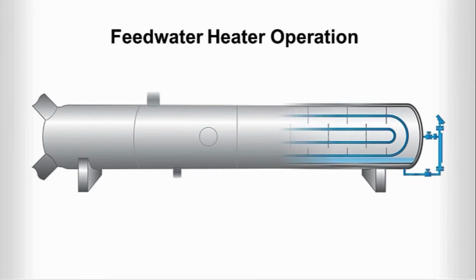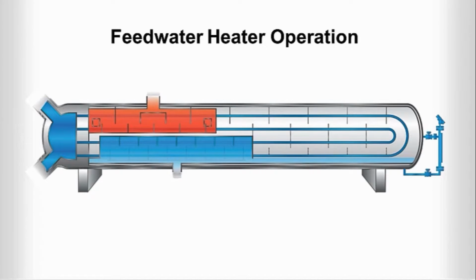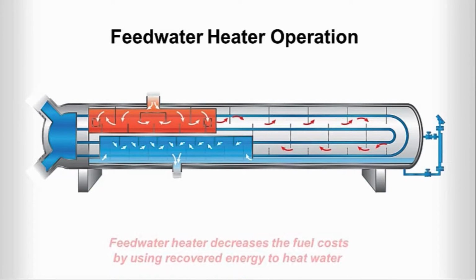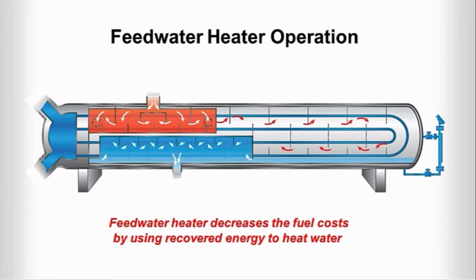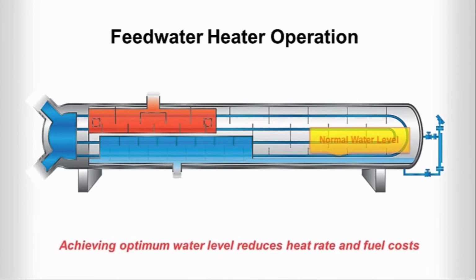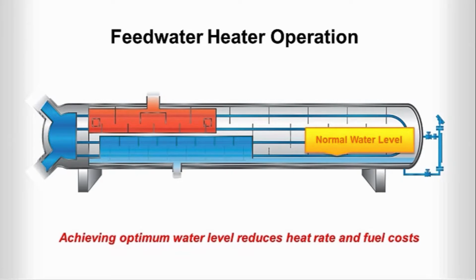Feedwater heaters use the heat of condensation to preheat water to the correct temperature for the boiler. During this process, shell and tube heat exchangers allow feedwater to pass through the tube side and extract steam from the turbine to the shell side. The primary benefit of this process is that the feedwater heater decreases the fuel costs by using recovered energy rather than costly hot gas to heat the water. Achieving optimum water level in a feedwater heater is a critical component of maximizing energy transfer and minimizing controllable losses.